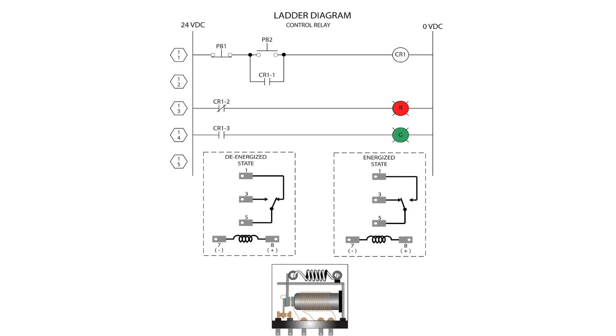The way the control relay is displayed on a ladder diagram is noted by a circle with a CR inside of it or on top. Relays will usually only have one coil but may have multiple contacts. They have a NC, normally closed, and a NO, normally open, contact.